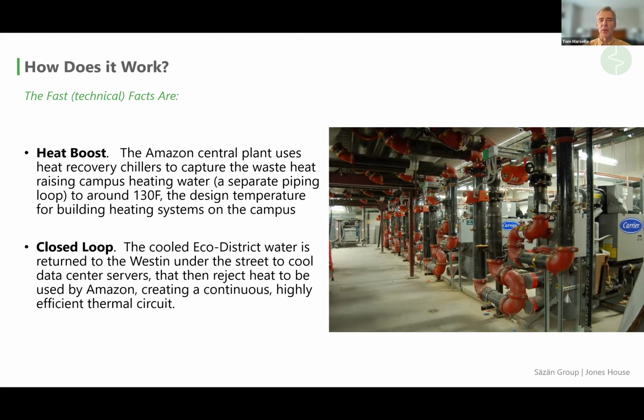When we designed the campus, we designed it for 130-degree heating water. So that differential between the 65-degree waste heat and that 130 is very achievable using a sort of conventional product on the market at the time. There are more products on the market now because we're really moving more in the direction of heat pumps, but this was a very off-the-shelf chilling product - very, very reliable, very well understood as something that would work for this application.